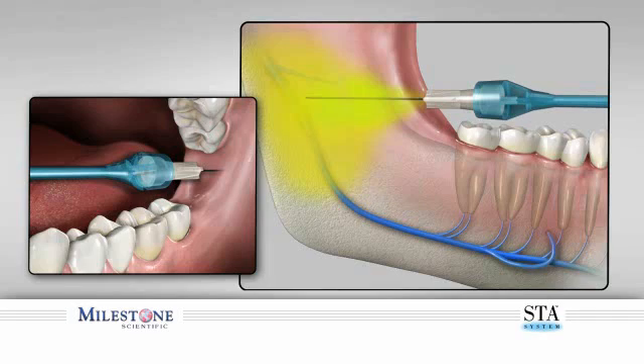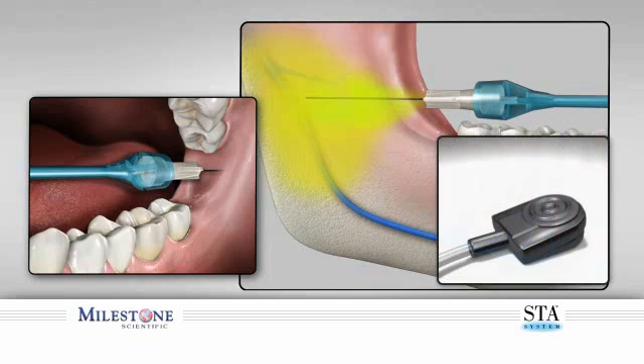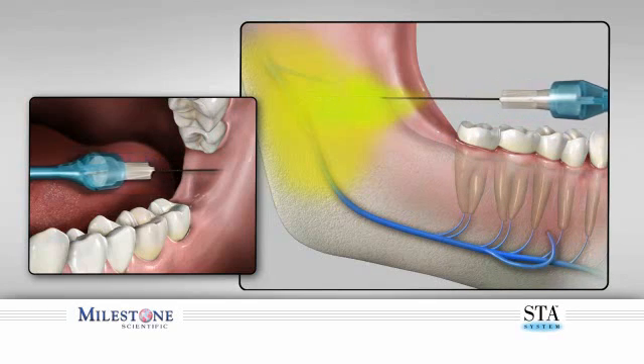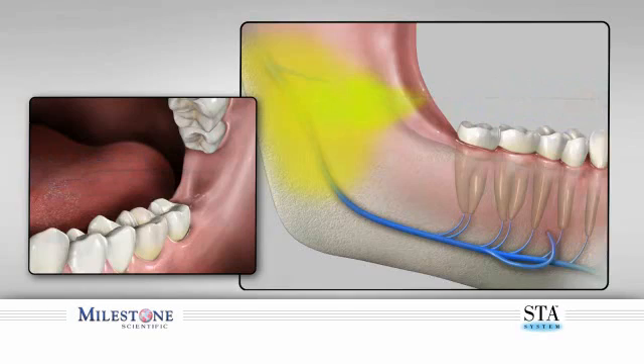To avoid anesthetic solution spray back into the patient's mouth, perform the following. While the needle is still embedded in the patient's tissues, depress and release the foot control pedal. Count three beeps after releasing the foot control, then totally remove the needle from within the patient's mouth. Direct the needle away from the patient, as a small amount of anesthetic solution may still be present.